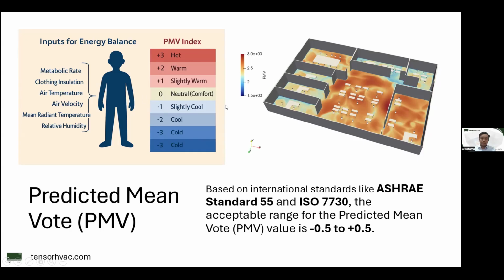So if the total calculation is zero, we will feel that the room is quite neutral or comfortable. But if the value is more than zero, like 0.5 or 1, it will be warmer. Or if it is a negative value, it tells us that the temperature is cold. So of course we want to design the PMV to be zero. And of course we cannot achieve a zero value everywhere. So ASHRAE 55 suggests a value in the range between minus 0.5 and 0.5. I will tell you how to calculate this later, but this is the idea.